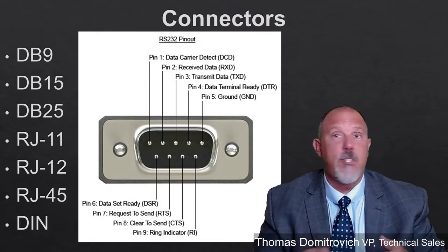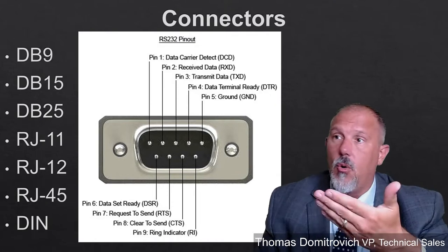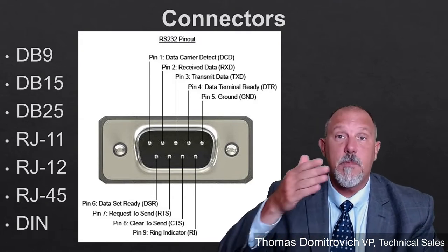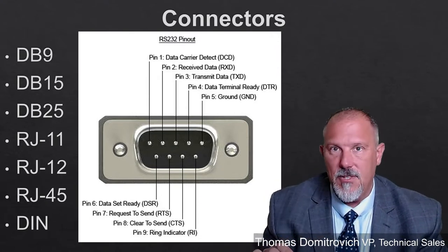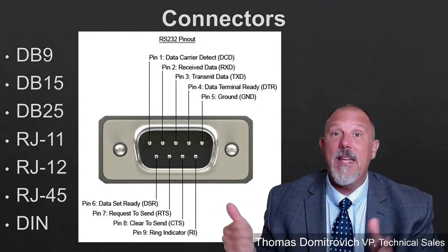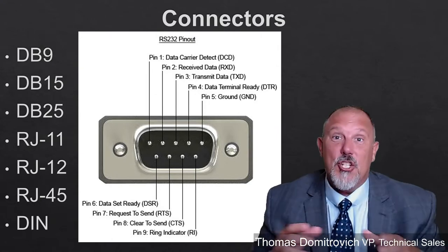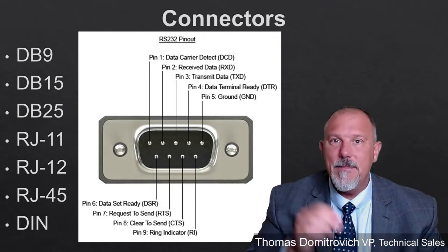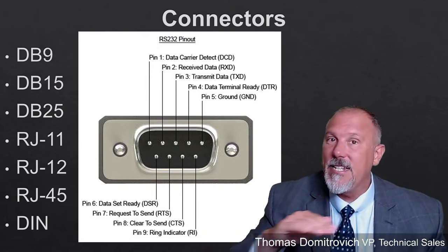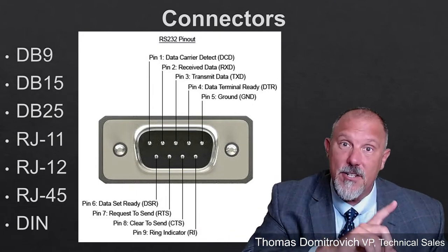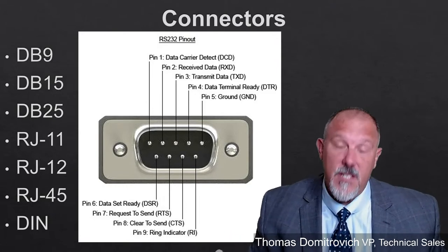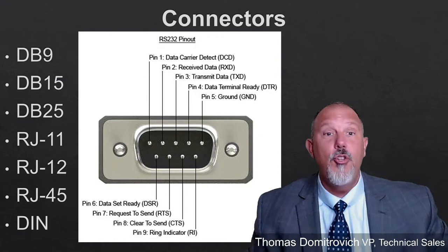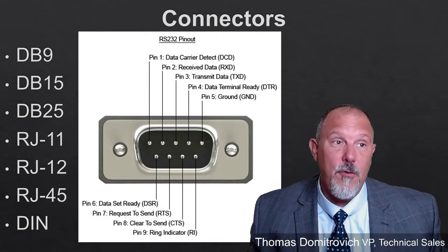You may see a DB9 connector and just say, hey, I'm going to run over to Home Depot, or to Best Buy, or go online and get 30 of these and just use them. And you find out, oh my goodness, no, this is a custom cable specific to that product and it needs a specific pinout. And by the way, you had to buy their cable. And maybe the manufacturer doesn't even tell you what the pinout is, unless you pry it out of their tech support guys so you can make your own cables. So you've got to understand there's sometimes a level of proprietary. There could be a proprietary protocol, or proprietary hardware, conductors, or data cables where the pinouts are specific to that product. If that's not something you want in your world, you don't want a proprietary protocol or proprietary pinouts, then you need to specify that, and you may find out that nobody can quote it.